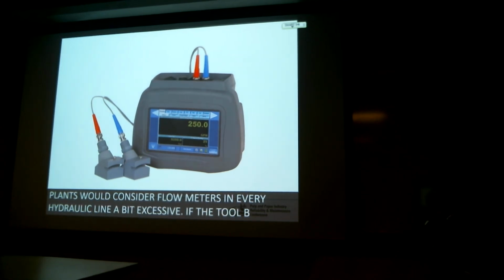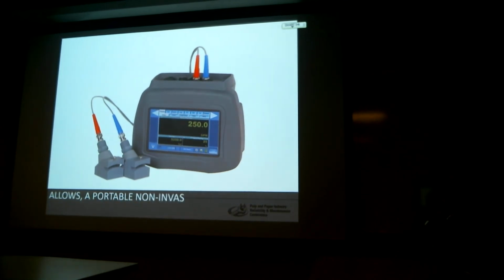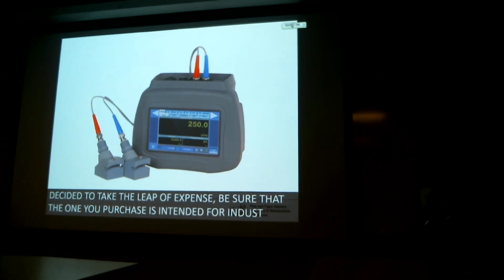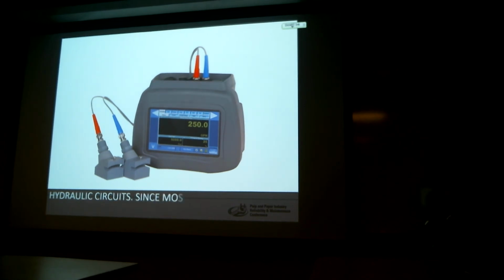If the tool budget allows, a portable non-invasive flow meter can be used to measure the flow rate of any hydraulic line, whether it's a metal pipe or a hose. These are quite expensive for hydraulic systems, but would not have to save very many hours of downtime to justify the cost. If it's decided to take the leap of expense, be sure that the one you purchase is intended for industrial hydraulic circuits. Since most of them measure the velocity of particulates in the liquid, the less expensive models will not work on industrial systems because hydraulic oil must be kept too clean for the particulate matter to be detected.